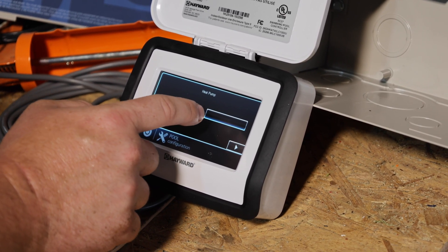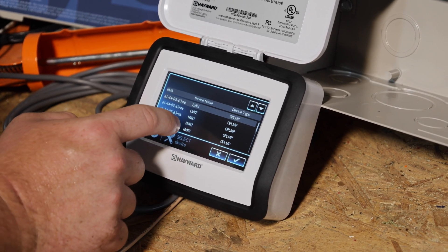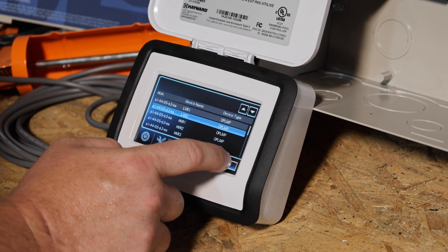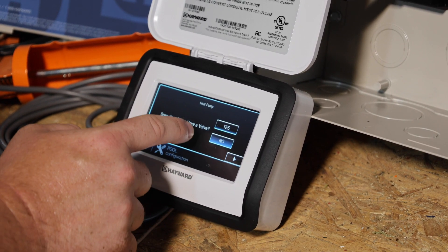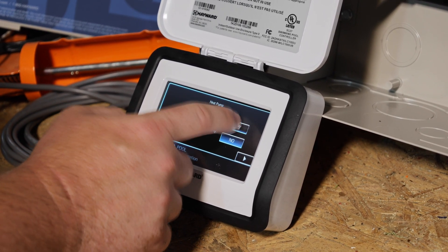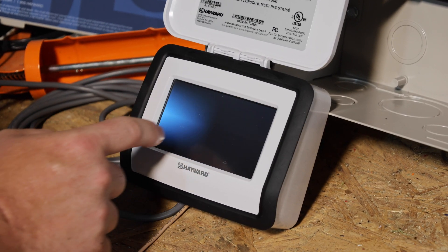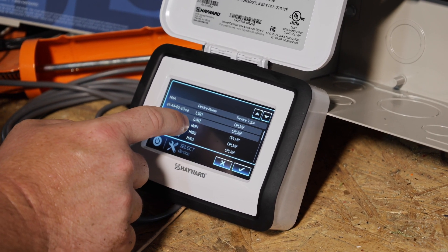Which relay is it wired to? In this case, I'm going to pretend that I wired the heat side up to LVR2. Right arrow. Does the pump have a valve? No. Does the heat pump support cooling? Yes, if you have the chiller. Right arrow. Which relay is the cool side wired to? I'm going to select as if we wired this into high-voltage relay one.